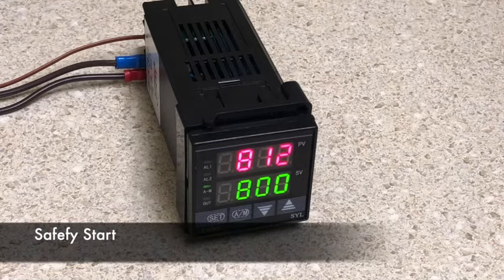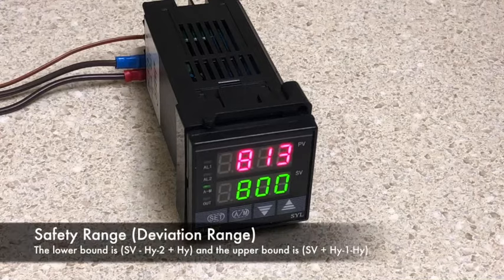This feature allows us to program a temperature range to make sure that the timer will only start counting once the measuring temperature falls into that range. This particular range is called a deviation range or safety range. This range is defined by deviation alarms and the hysteresis band.